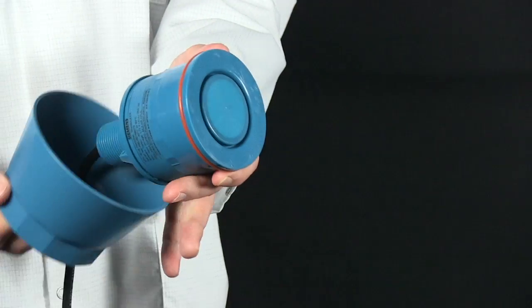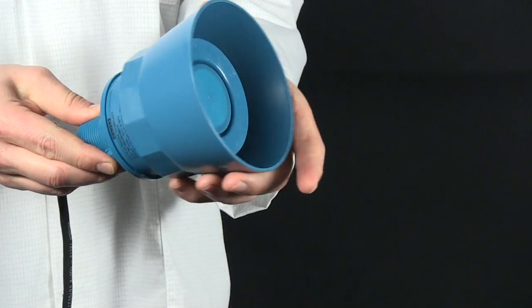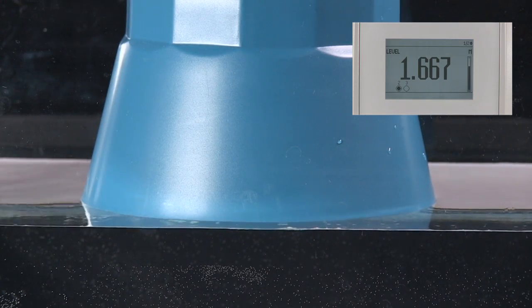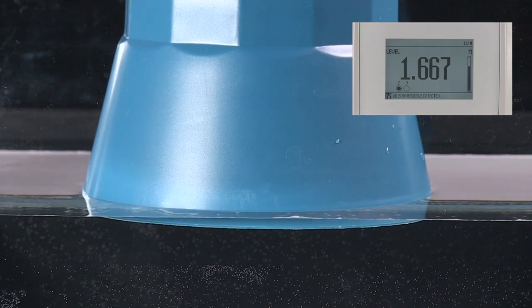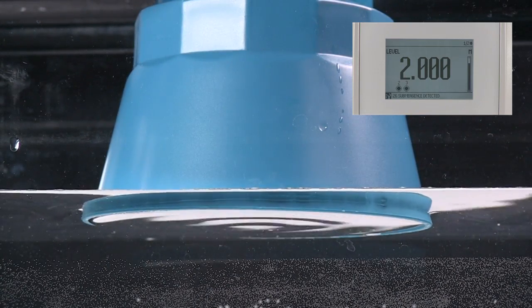A simple remedy is using a submergence shield. A submergent shield on a transducer creates an air pocket in front of the transducer face when it becomes submerged. The controller senses this condition and recognizes it as flooding.